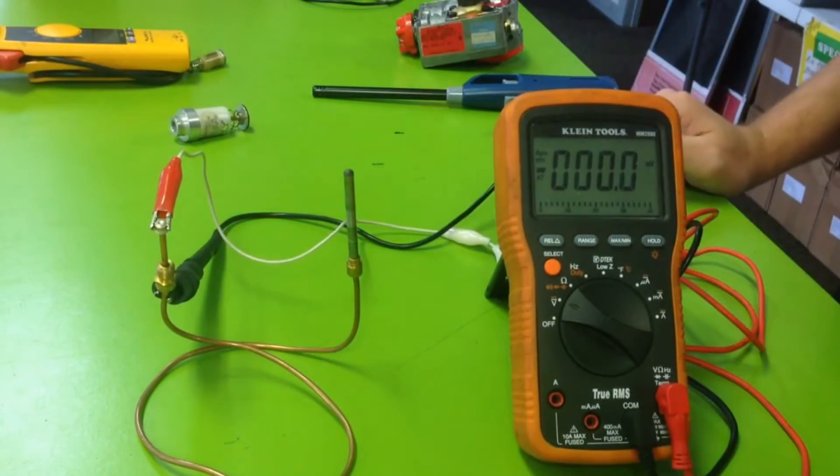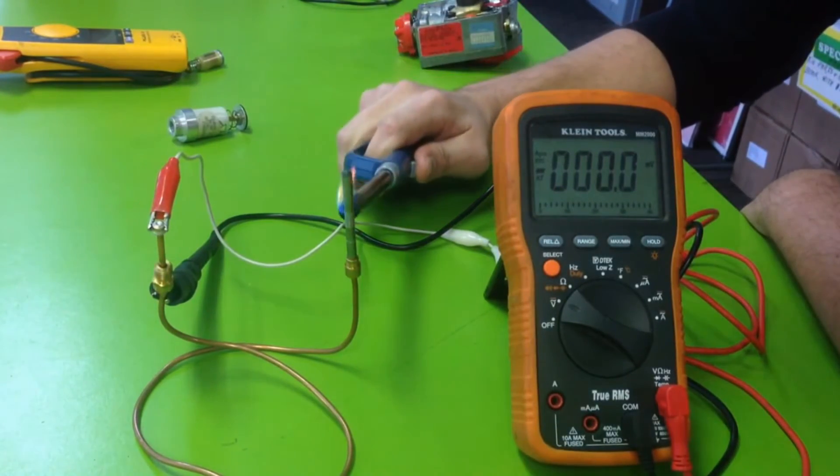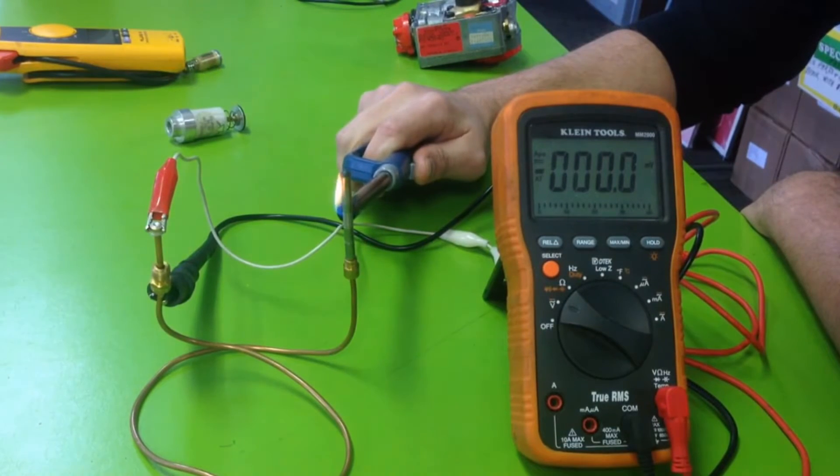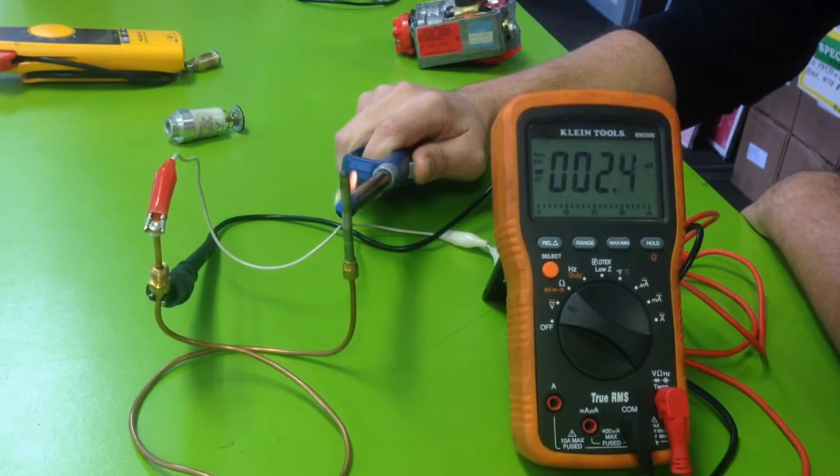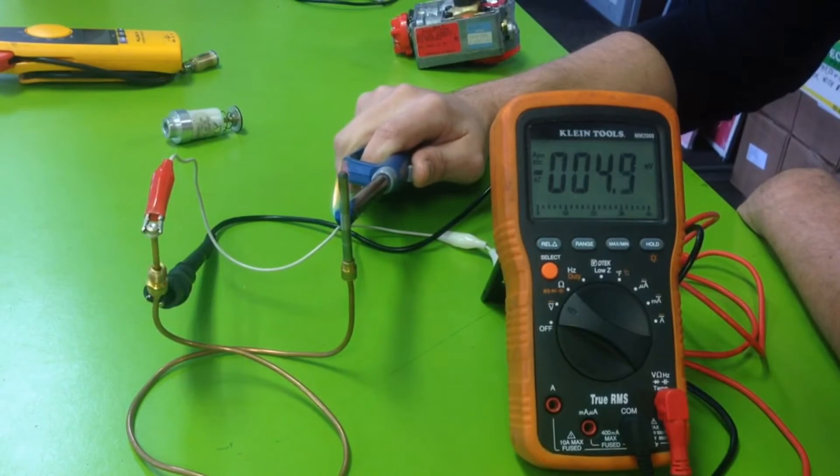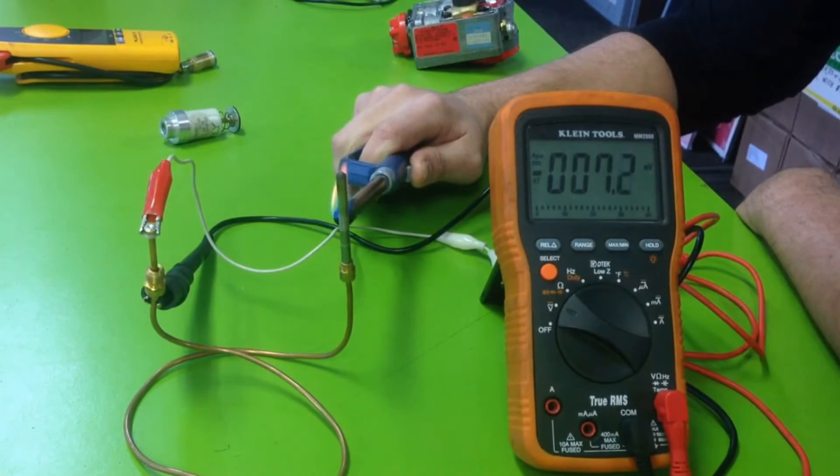Then all you do is take heat and apply it to the thermocoupler, and you should see numbers being generated. I'm generating 4, 5, 6 millivolts - basically I'm making millivolts.